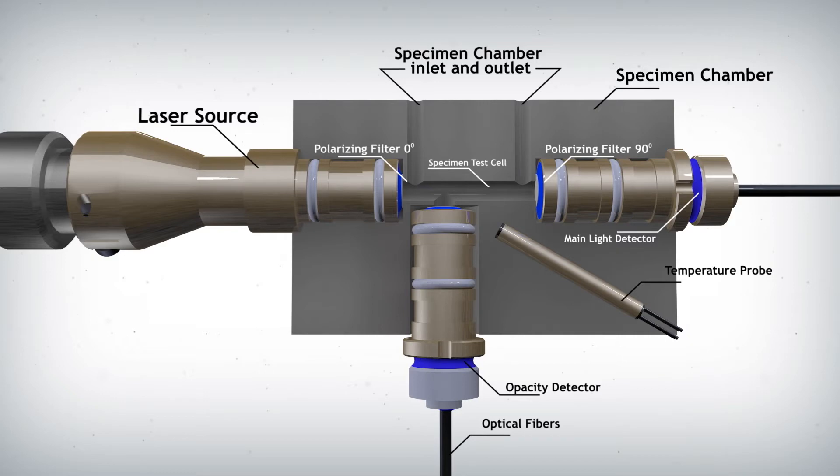Because the polarization filter located on the laser source is 90 degrees out of phase with the polarization filter on the main detector, no light can penetrate the second filter and reach the main detector when the specimen test cell is empty or when there are no crystals in the jet fuel sample.